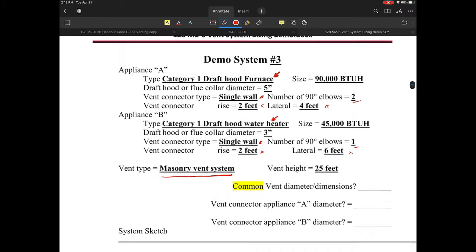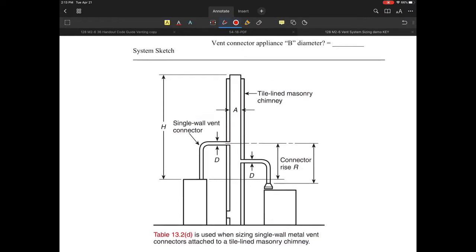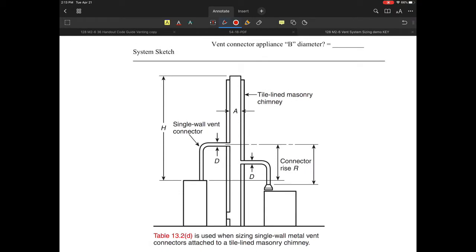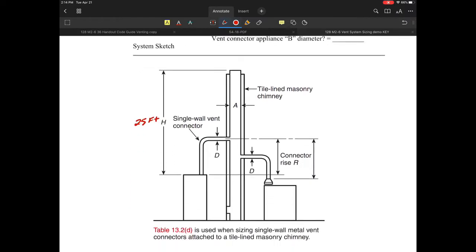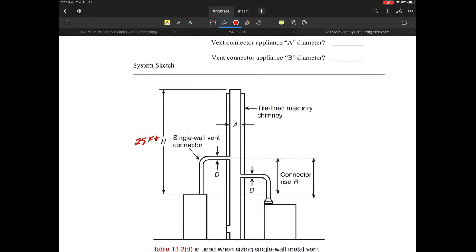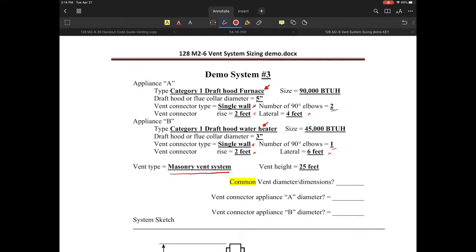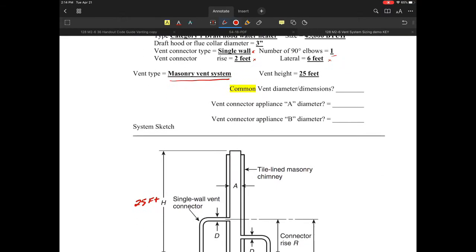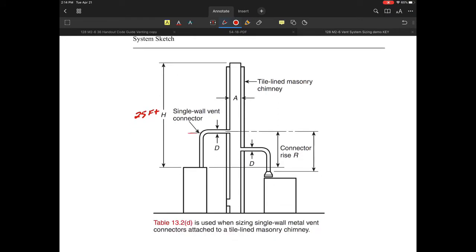We also have a vent system that's 25 feet in height. The chimney height is determined from the taller of the two appliances, so in this case we have 25 feet. We're dealing with the first connector. The smaller of the appliances has to vent higher — that was one of the rules from the handout on code venting. The draft hood water heater is a 45,000 BTU unit with a two-foot rise.